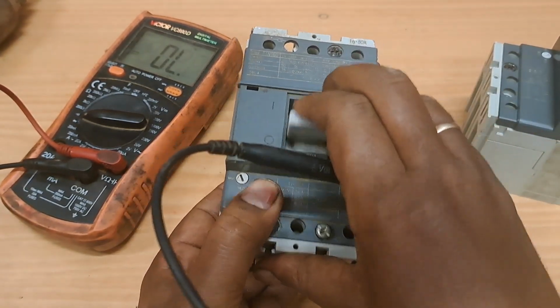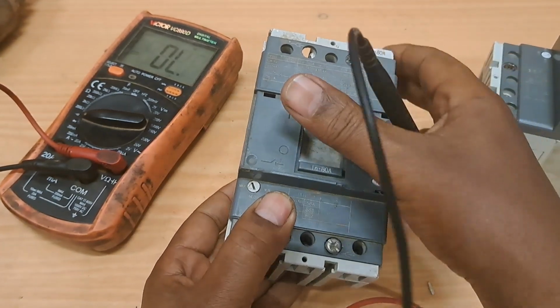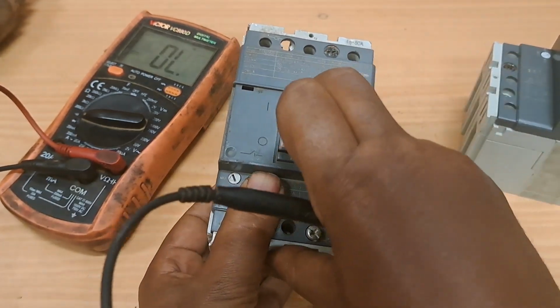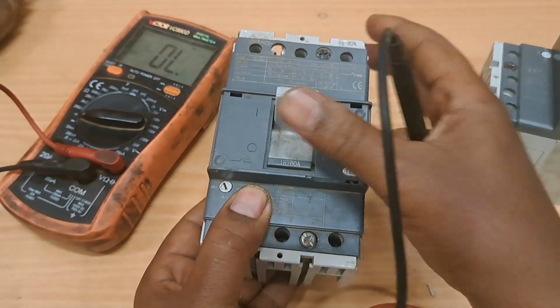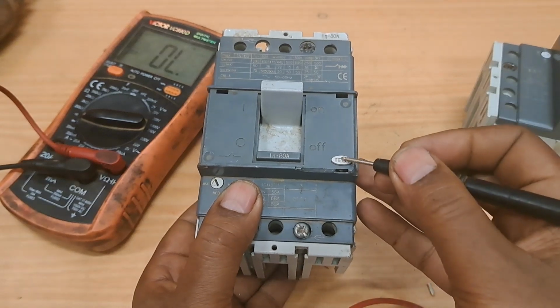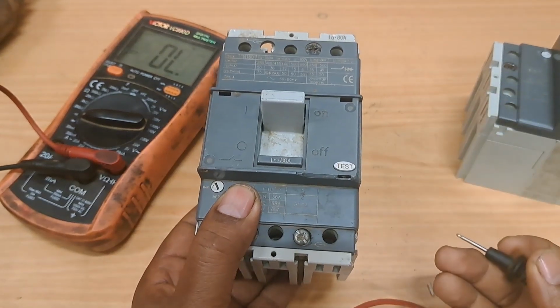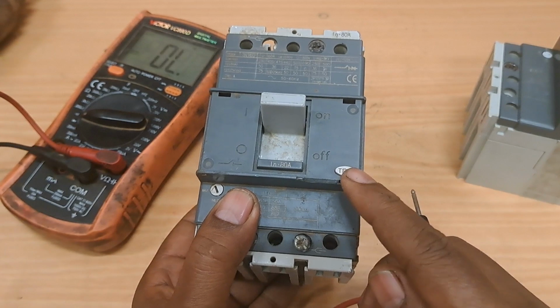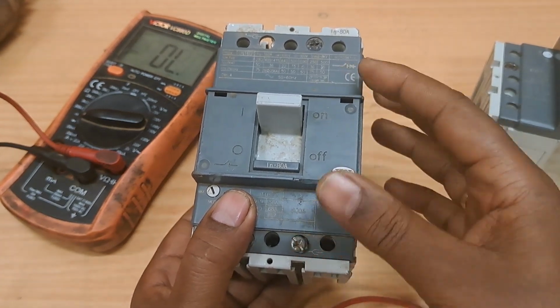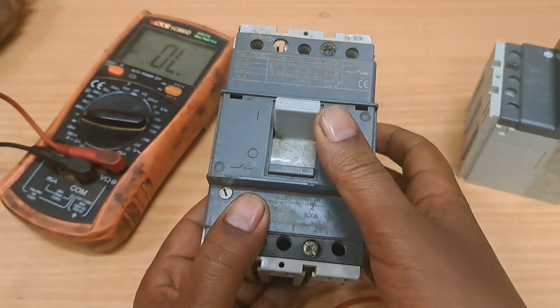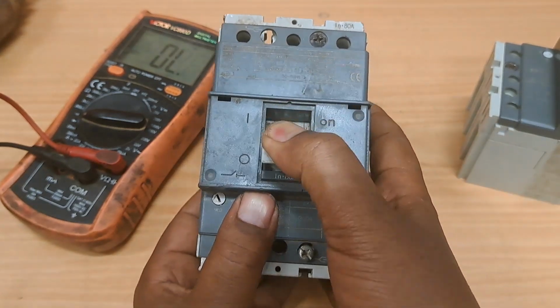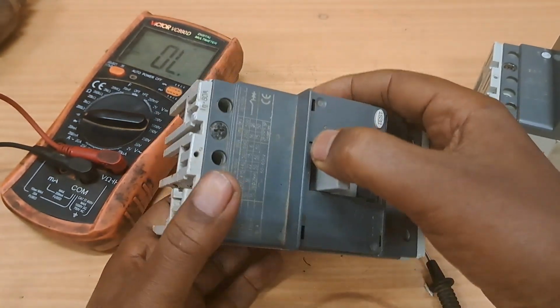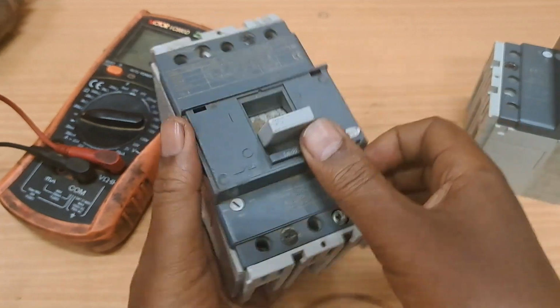To engage it, put it on off and reopen it and press it right here. See? So this is the test button with which you can see if it is snapping out of continuity when there is high current flow or not. So this is how you check the operation of this breaker.